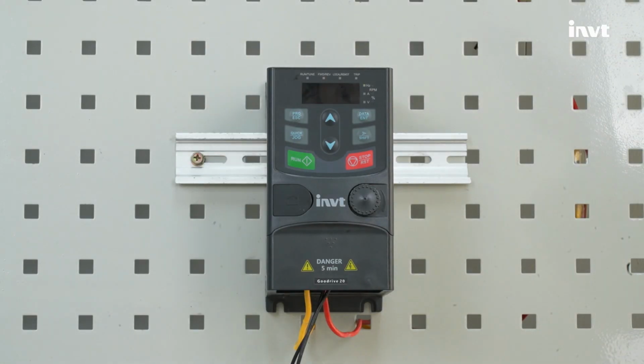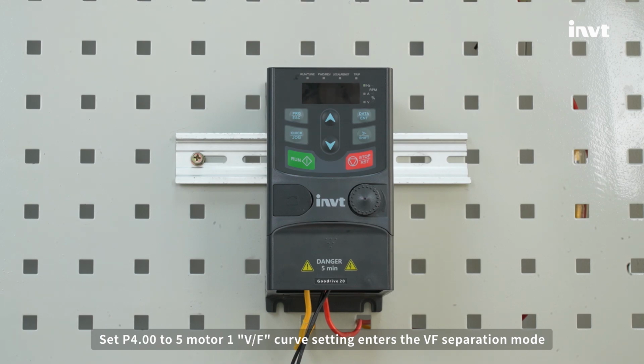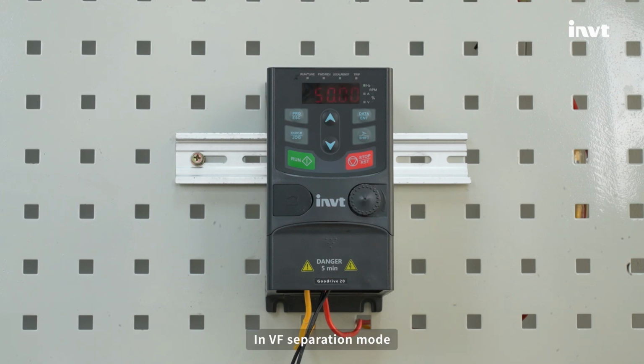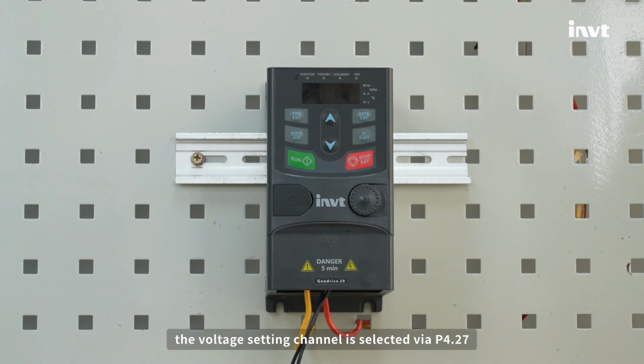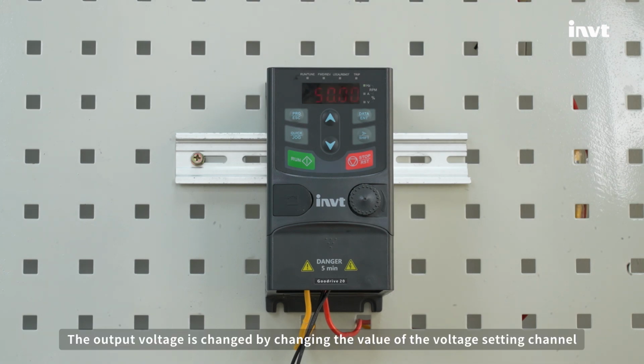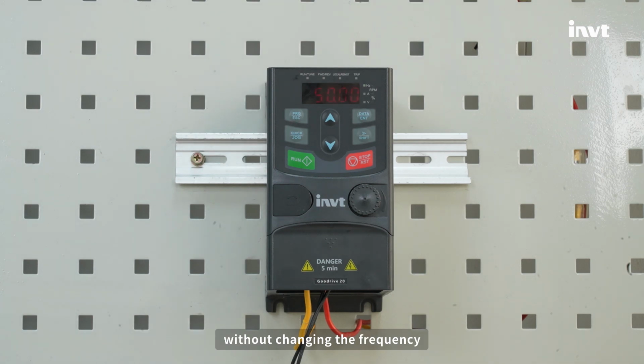V/F separation. Set P4.00 to 5. Motor 1 V/F curve setting enters the VF separation mode. In VF separation mode, the voltage setting channel is selected via P4.27. The output voltage is changed by changing the value of the voltage setting channel, without changing the frequency.